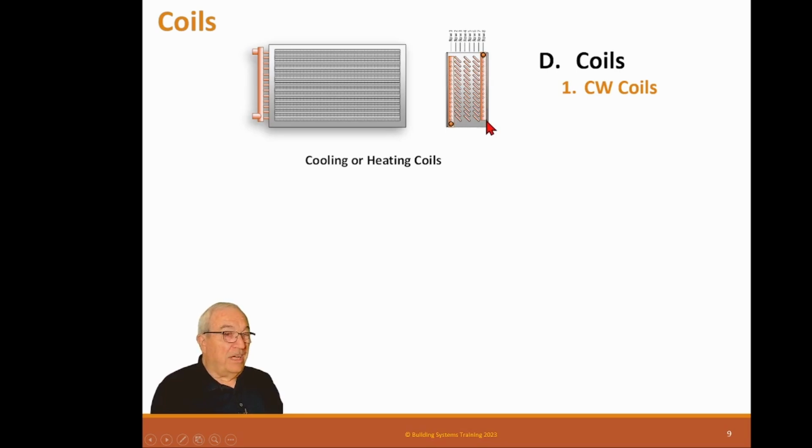Normal is 1 to 8 rows. Normally for chill water, it'd be 4 to 8 rows maybe. And the number of rows determines how much heat you're going to transfer, along with the fin spacing. And fin spacing can be from 8 to 24. I think I have it in here. It's 1 to 10 rows for chill water, 6 to 24 fins per inch.